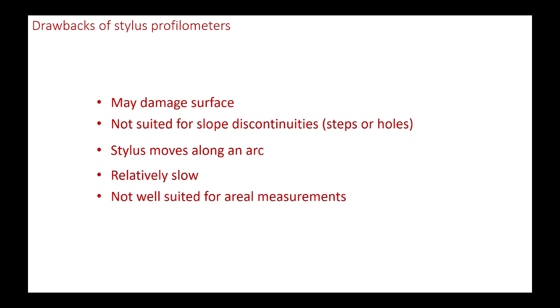Another major drawback is the slowness of measurement, due to a speed which is generally a few hundred micrometers per second, up to a few millimeters per second at most. This makes it impractical to adapt to areal measurement with a Y table. Measuring a surface of a few hundred parallel profiles can take several hours. We will then prefer optical profilometers, which are faster but whose lateral measurement field is more restricted.